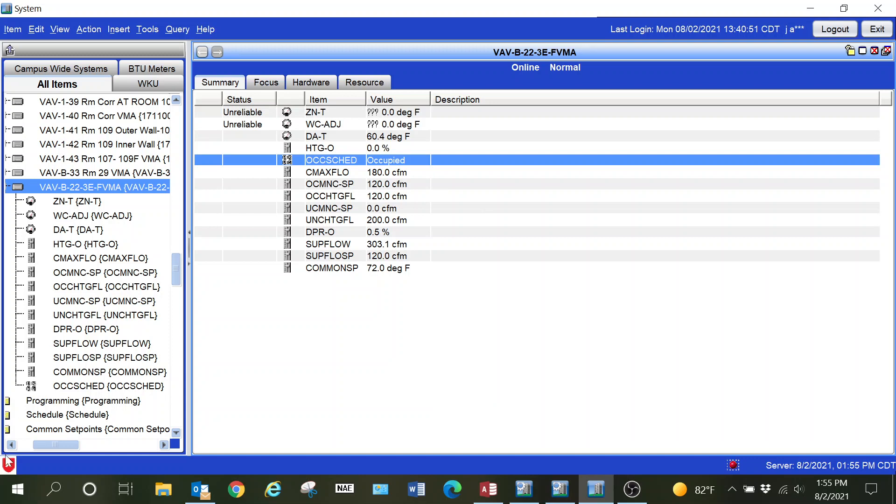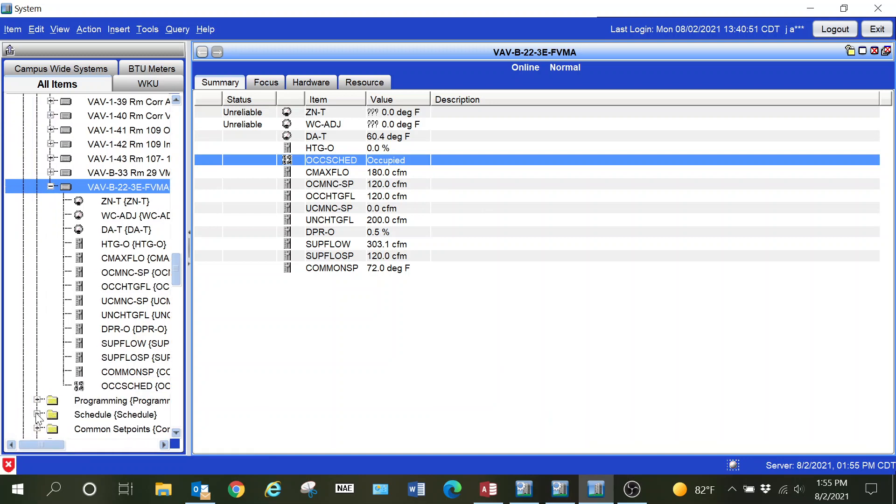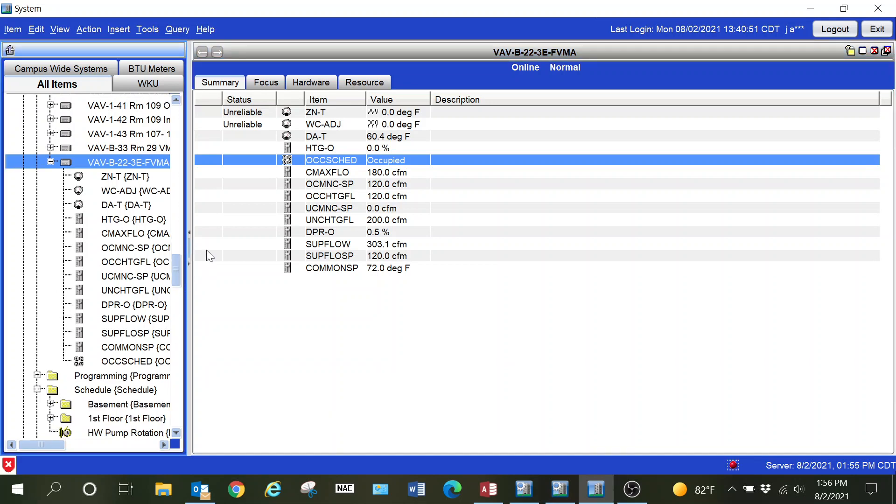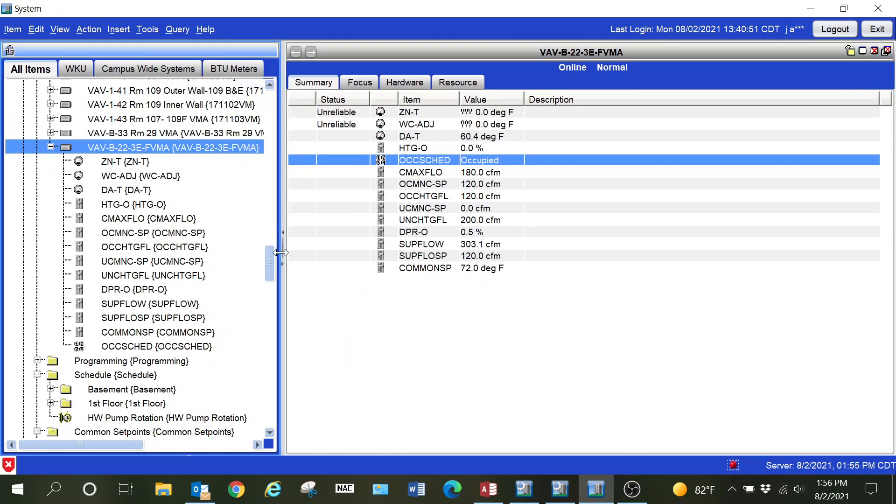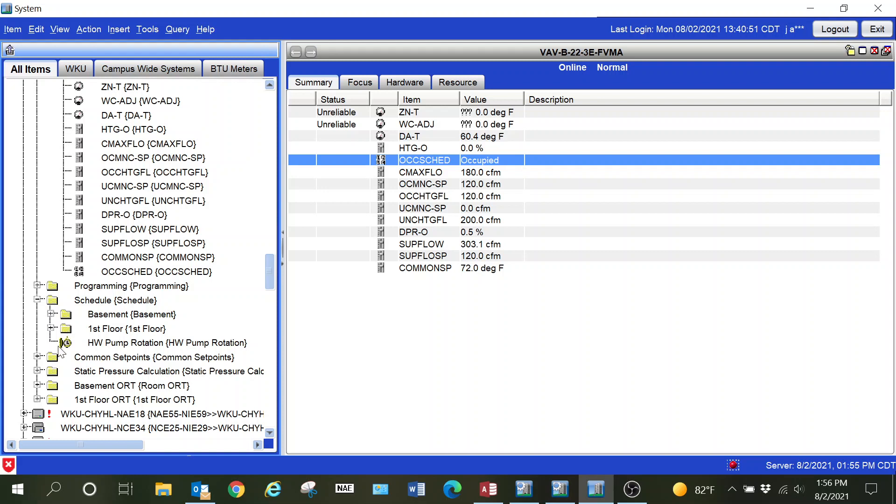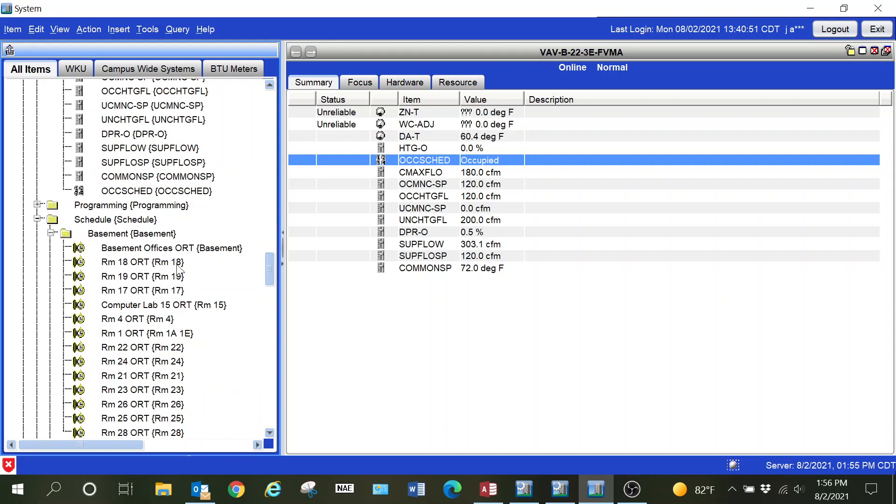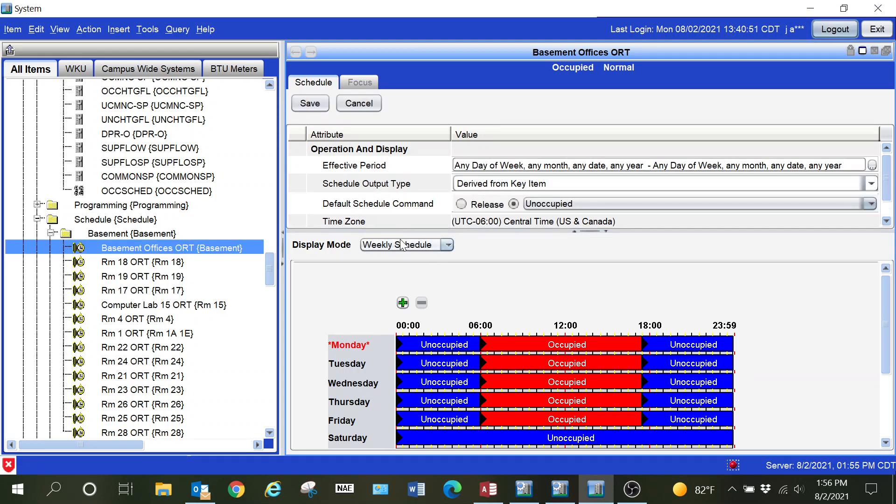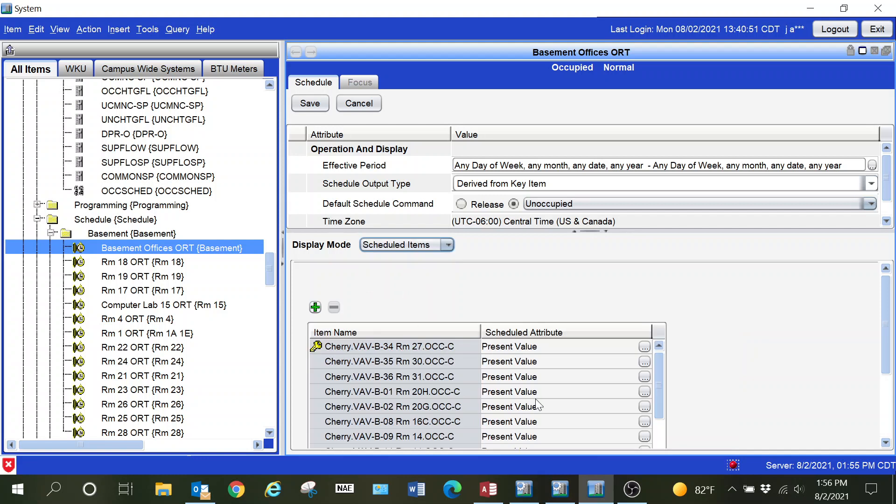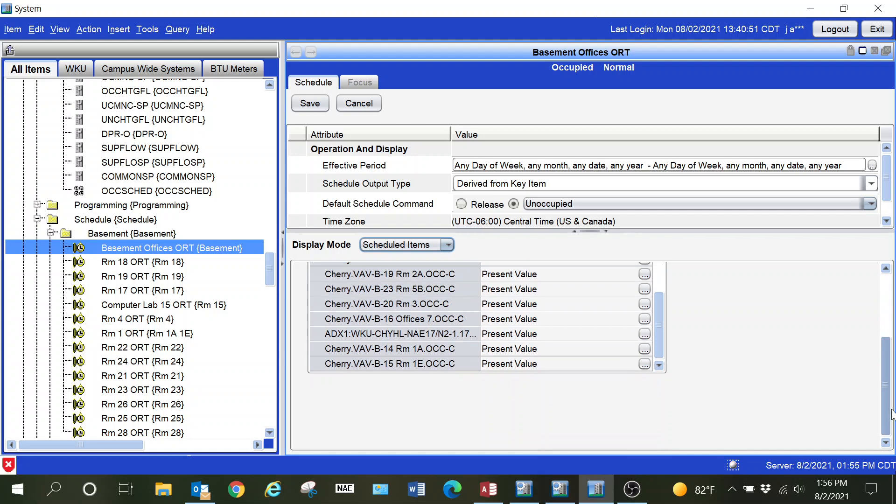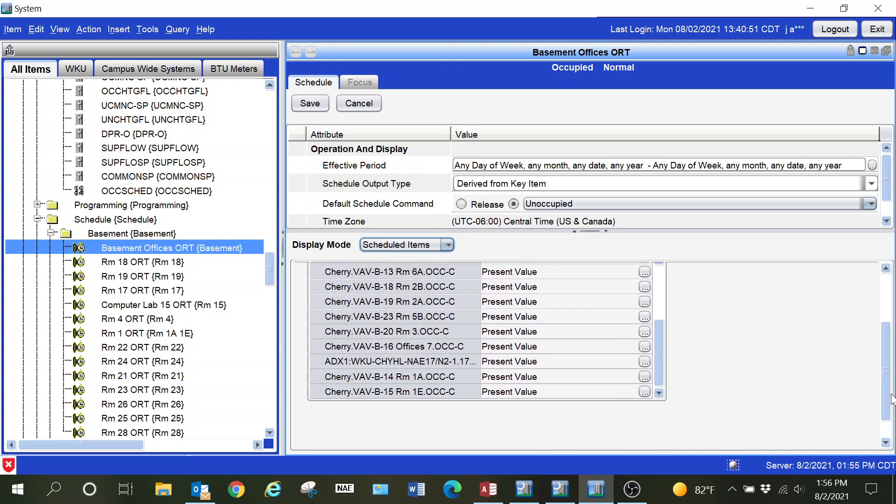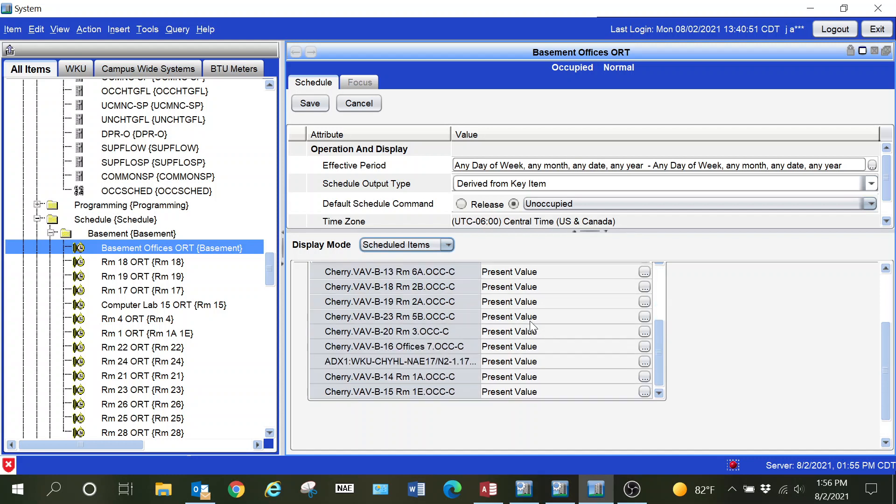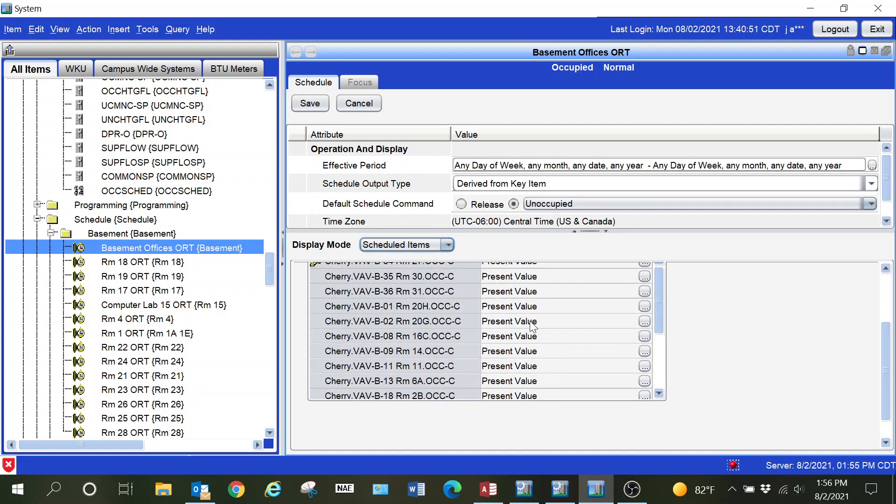The minimum and maximum values on your flow set points and things like that may come in showing unreliable because of the way those points are configured. You can simply change that minimum and maximum value and it should bring those back to reliable. When you replace an older device with a newer generation device, you're going to have to go through your schedules and logic.